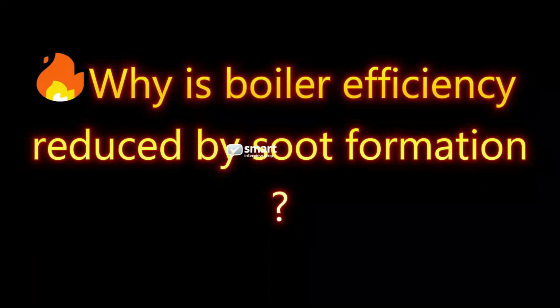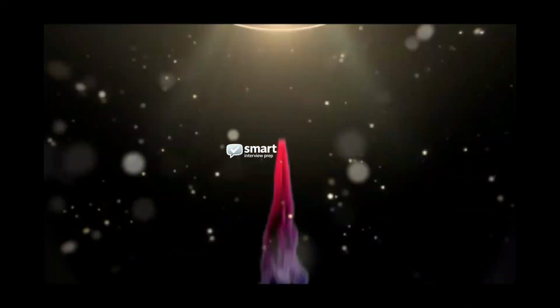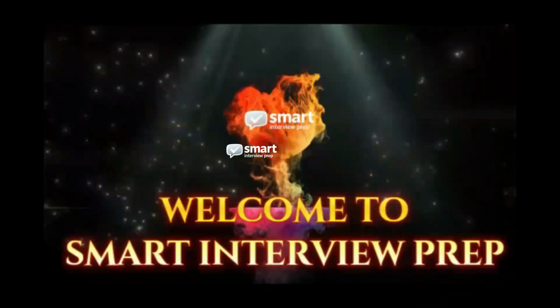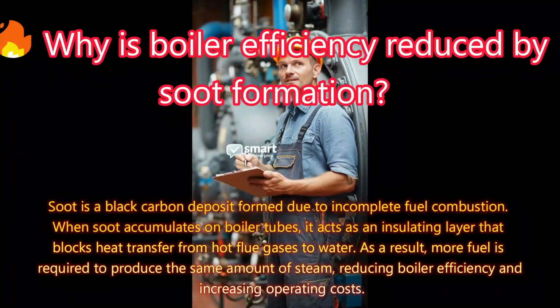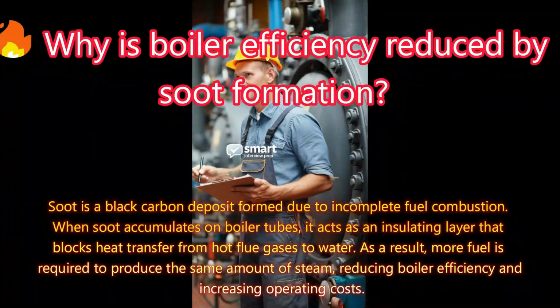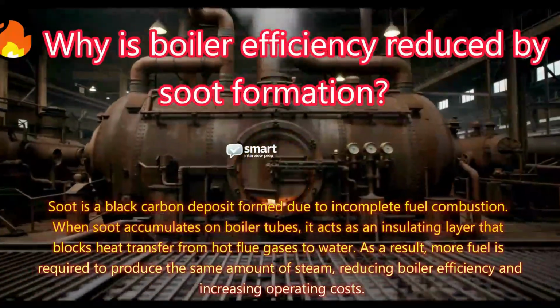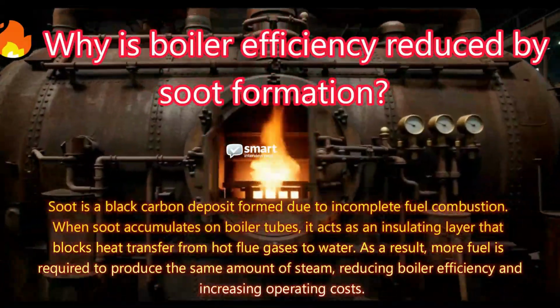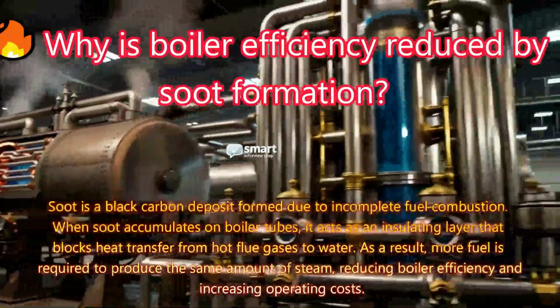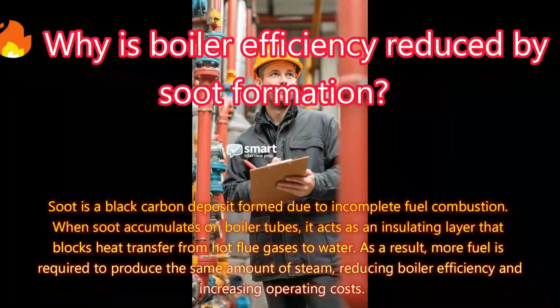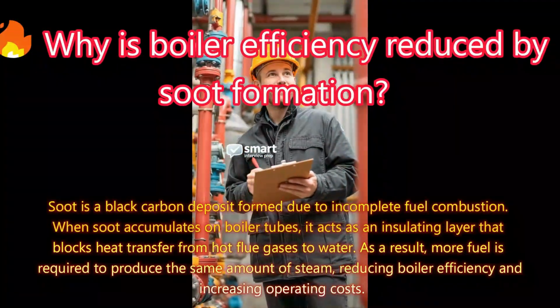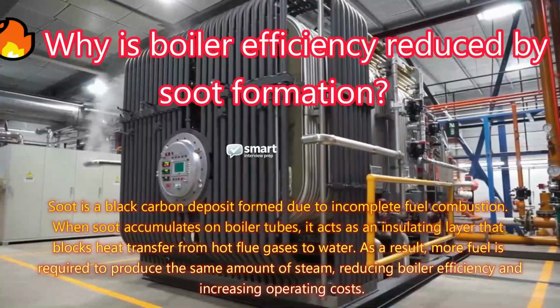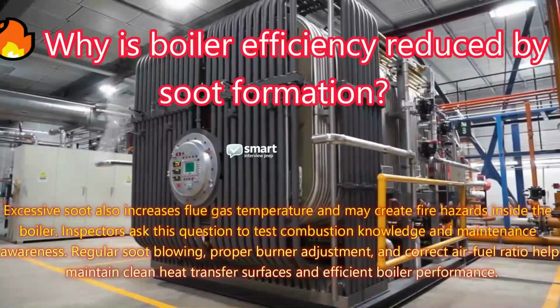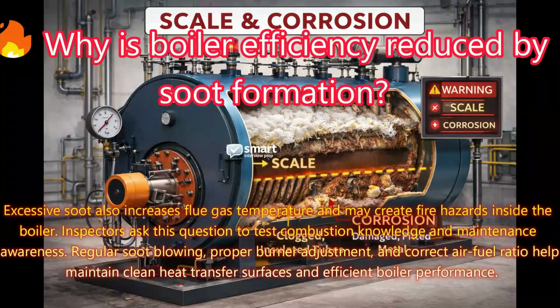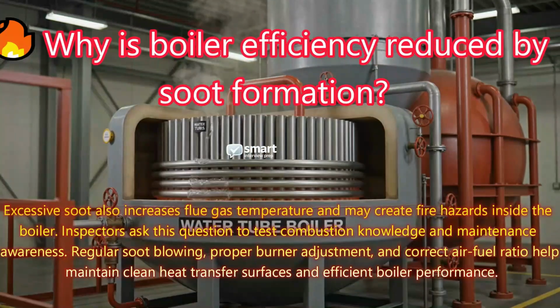Why is boiler efficiency reduced by soot formation? Answer: soot is a black carbon deposit formed due to incomplete fuel combustion. When soot accumulates on boiler tubes, it acts as an insulating layer that blocks heat transfer from hot flue gases to water. As a result, more fuel is required to produce the same amount of steam, reducing boiler efficiency and increasing operating costs. Excessive soot also increases flue gas temperature and may create fire hazards inside the boiler.